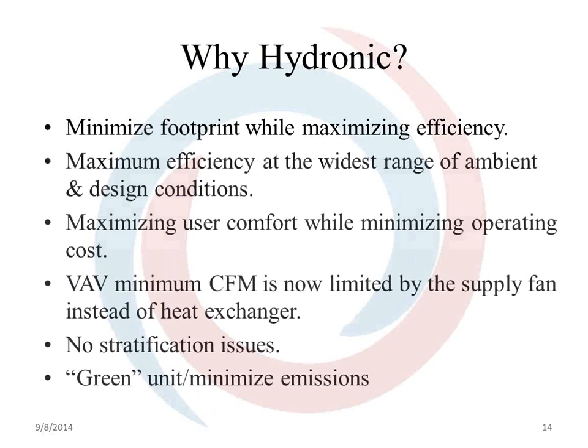At low CFMs in a typical system, as you turn down the CFM, the delta T at the supply increases. With a modulating gas control, you can turn down the gas valve, but once you hit the minimum firing rate, you risk cracking the heat exchanger or tripping the high limit if you continue lowering the CFM. Depending on the controller used for the unit, the minimum CFM is either defined by the maximum discharge temperature at full fire, or in a more complex controller, the maximum discharge air temperature at minimum fire. The limiting factor on Xcelon is the minimum speed of the fan and the VFD.